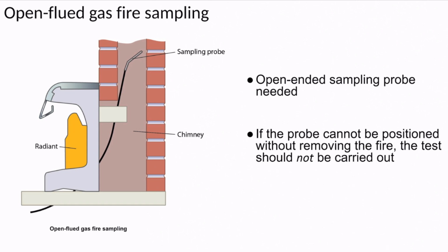Now, what throws a lot of people out is what happens with an open flued gas fire that's attached to the wall. As you can see from this picture, an open-ended sampling probe is needed. However, in pretty well 99 out of 100 cases, there is no way to get the probe into the chimney without taking the fire off the wall. So the rules state that if you cannot put the probe into position without removing the fire, then just don't carry the test out.